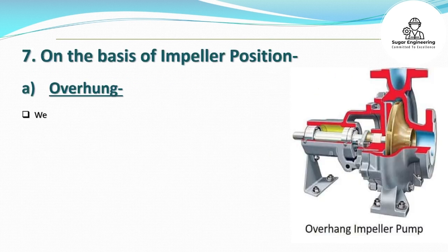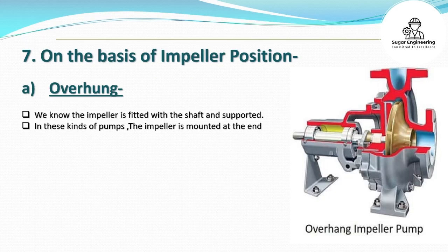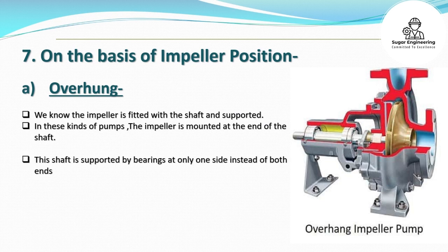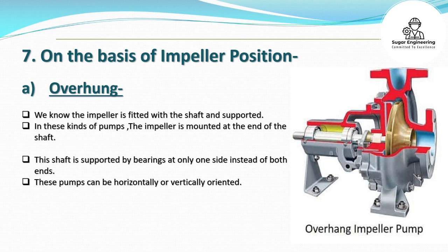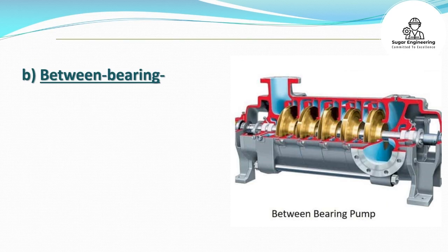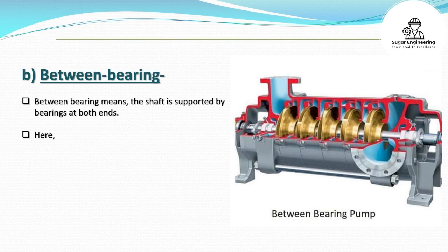On the basis of impeller position: A. Overhung — the impeller is mounted at the end of the shaft. The shaft is supported by bearings at only one side instead of both ends. These pumps can be horizontally or vertically oriented. B. Between bearing — the shaft is supported by bearings at both ends, and the impeller is located between the bearings.